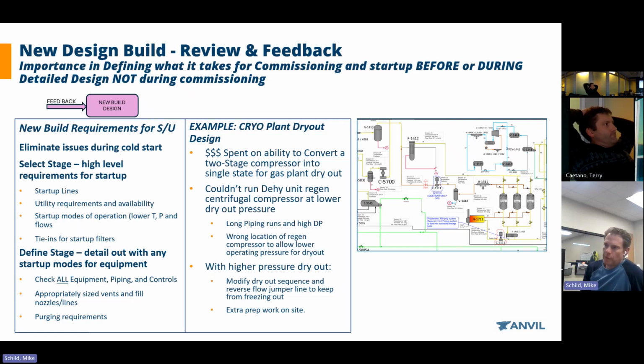Also, I probably would have argued that you can run a two-stage recip at these lower pressures just because it's for a short period of time. We really don't like to do that because we can damage the valves on the compressors themselves. But again, these dry outs are 2 to 3 days. It's not going to damage these valves. We just don't want to do that long term. So I probably would have argued you don't really need to single stage it. It is nice to be able to do it, but we had a spaghetti of piping and a lot of valves, 12-inch gate valves that have to open and close, even if we wanted to single stage it.